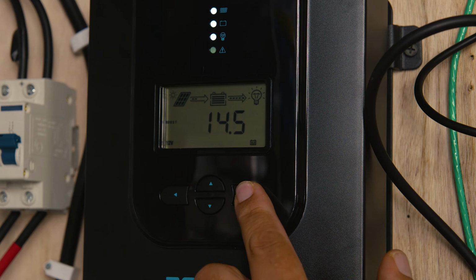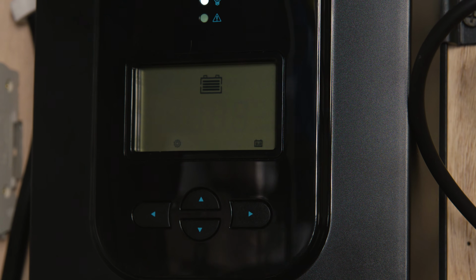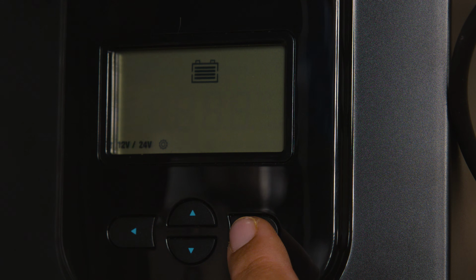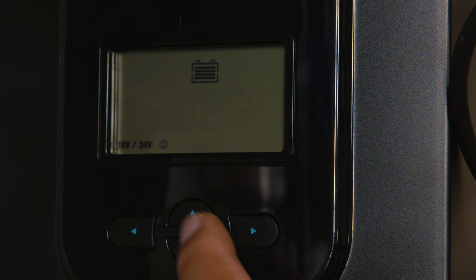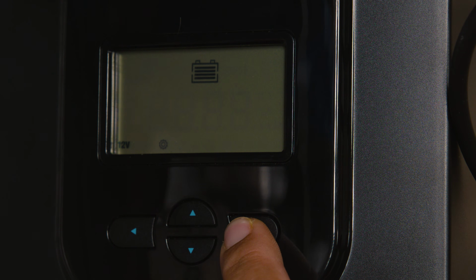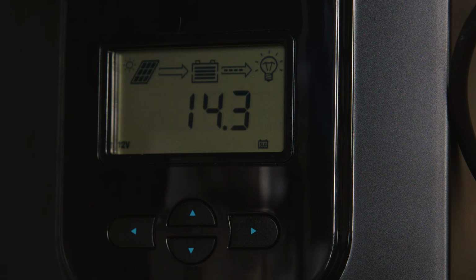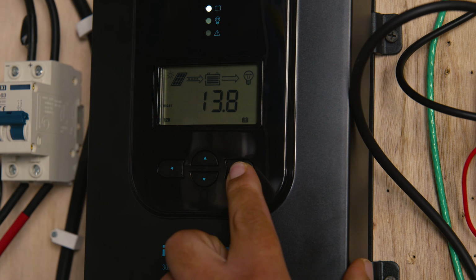The first thing we're going to do is choose our battery. If you hold the right arrow button for a minimum of 3 seconds, we should go into that screen, and remember, you want to do this from the main screen. On the left side, we're going to see the battery voltage. You could choose from 12 volts, 24 volts, or if you leave it in 1224, it would automatically choose the correct voltage for you.